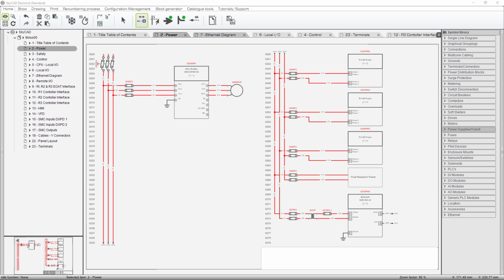Circuit breakers have a little toggle switch on them, and if you're using this for a disconnect, then that means that you have a mechanical device on the door that you can turn this circuit breaker off from outside with the door closed. Or if you're using a fusible disconnect, you've got a mechanical mechanism, and there's 2 types: through the door or flange mount. The flange mount, part of it mounts to the enclosure and the other part mounts to the back panel, the back plate. Whereas a through the door, you mount the fusible disconnect on the panel, and then it's got a square rod that sticks out far enough that it'll go through the door when the door is closed. Cut a hole through the door, mount the handle on it, you know, the rotating, what you might call the switch handle, and there you go.